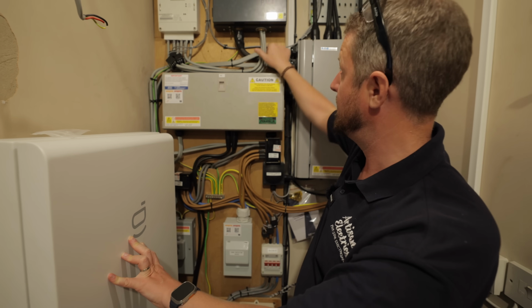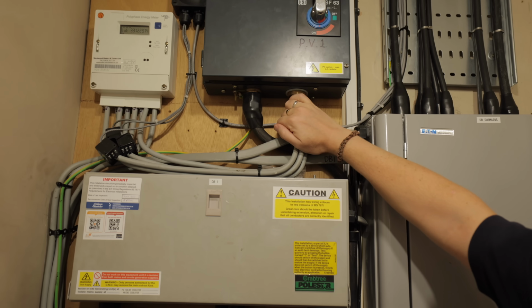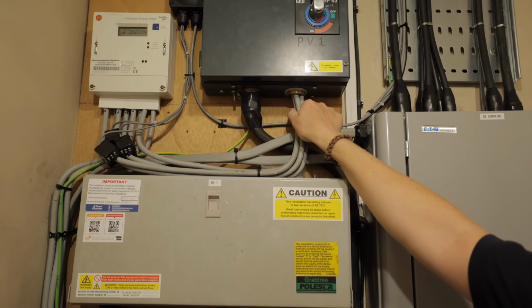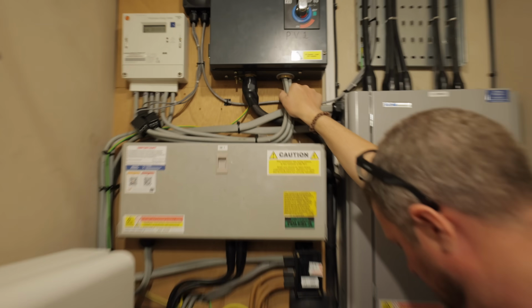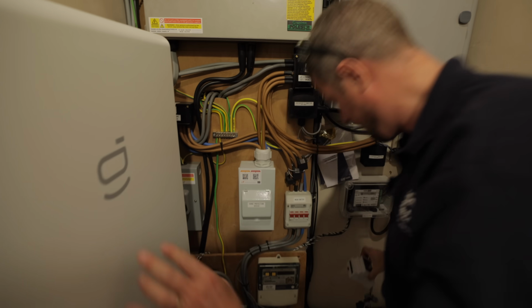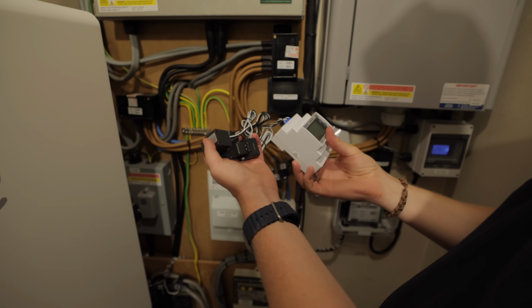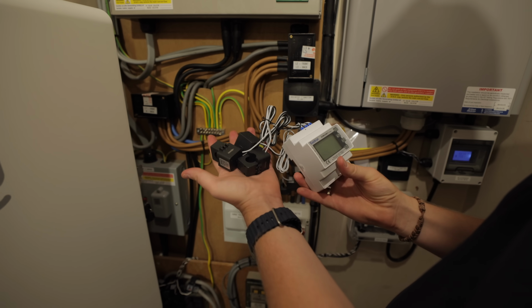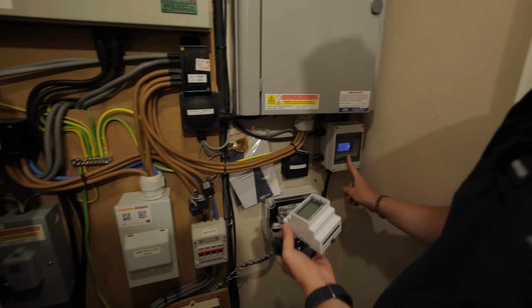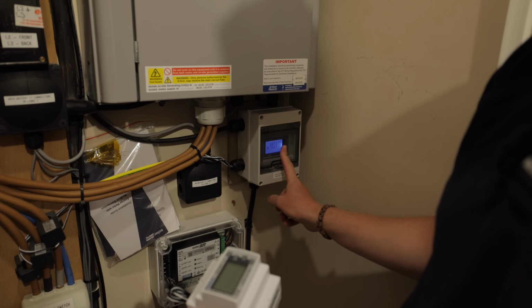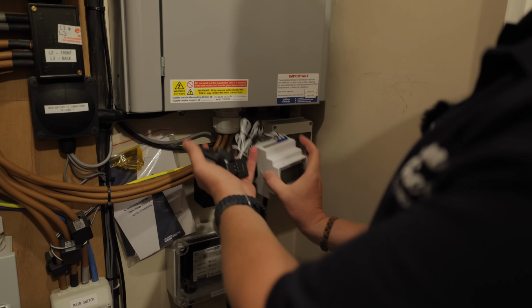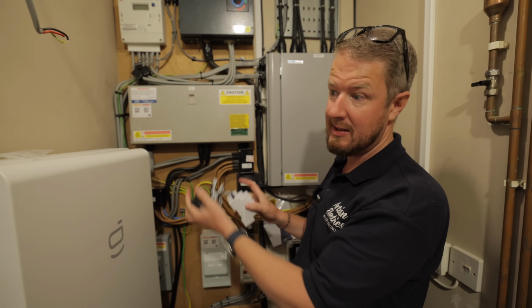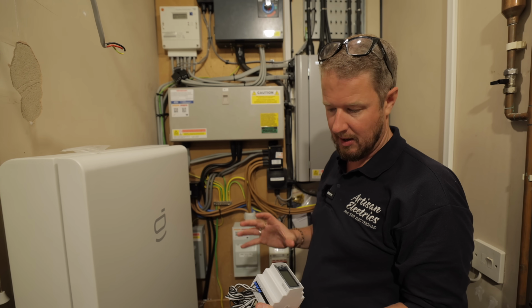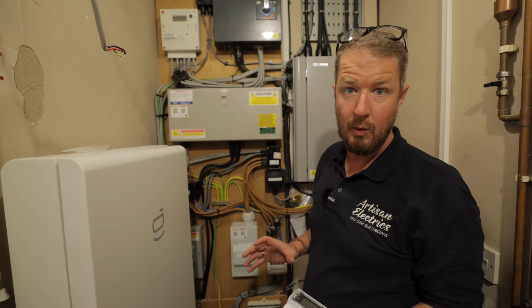The other thing we need to do is monitor the solar. This is the existing solar PV system - we've got about 40 kilowatts of solar on this site, and we're going to install this power sensor, which is basically a little Eastron meter. That's going to replace the existing meter for the Solis/PureDrive system we've ripped out, and it will monitor the existing solar PV system so we can see it in the Sigenergy app and know exactly what's going on.